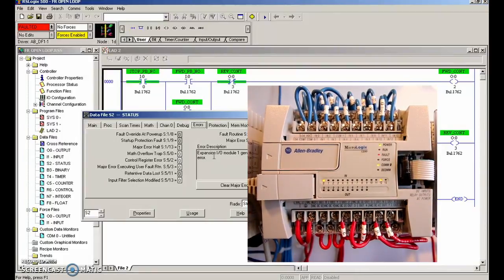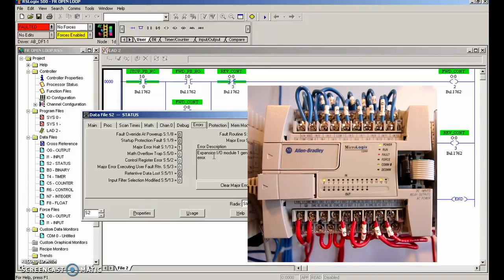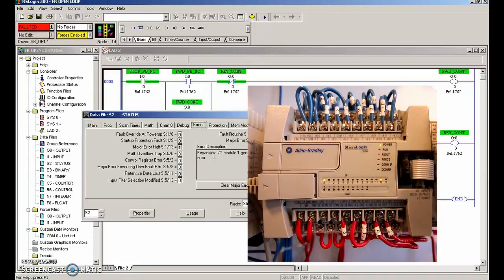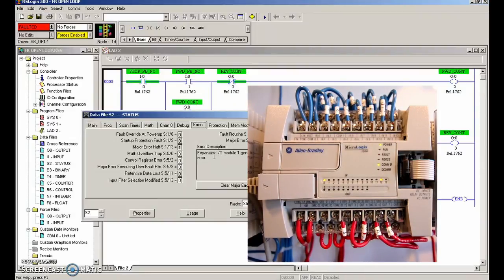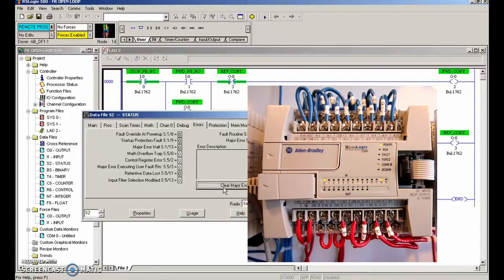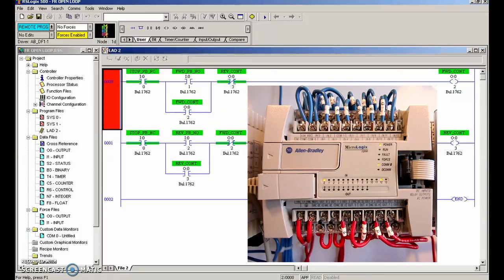That's what happens every time you forget to do your IO configuration. Beside the PLC there's an analog card — we're not making use of it but it is connected, so the PLC wants to know what it is. If we don't tell it, it's going to give us that fault. So what we're going to do is clear that major error and then go offline.